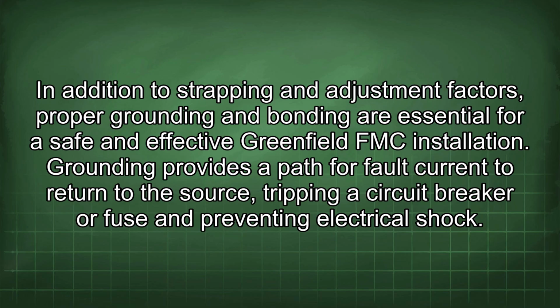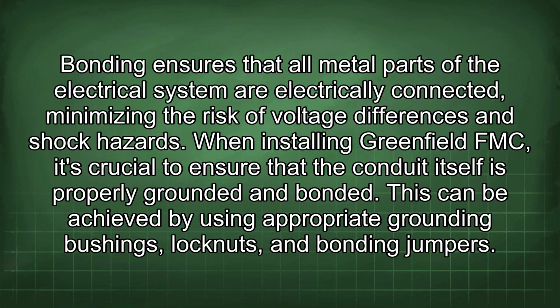In addition to strapping and adjustment factors, proper grounding and bonding are essential for a safe and effective Greenfield FMC installation. Grounding provides a path for fault current to return to the source, tripping a circuit breaker or fuse and preventing electrical shock. Bonding ensures that all metal parts of the electrical system are electrically connected, minimizing the risk of voltage differences and shock hazards. When installing Greenfield FMC, it's crucial to ensure that the conduit itself is properly grounded and bonded. This can be achieved by using appropriate grounding bushings, lock nuts, and bonding jumpers.